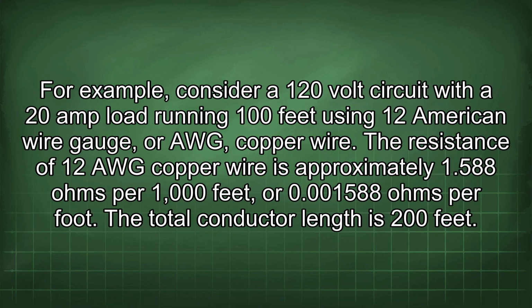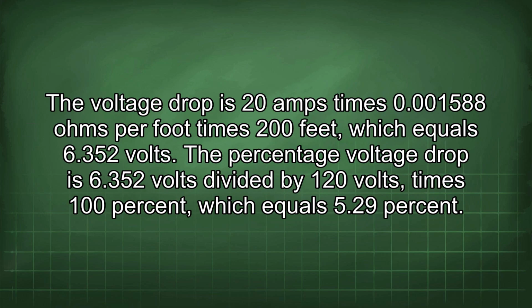For example, consider a 120 volt circuit with a 20 amp load running 100 feet using 12 American wire gauge, or AWG, copper wire. The resistance of 12 AWG copper wire is approximately 1.588 ohms per 1000 feet, or 0.001588 ohms per foot. The total conductor length is 200 feet. The voltage drop is 20 amps times 0.001588 ohms per foot times 200 feet, which equals 6.352 volts. The percentage voltage drop is 6.352 volts divided by 120 volts times 100%, which equals 5.29%.